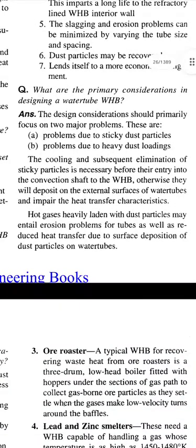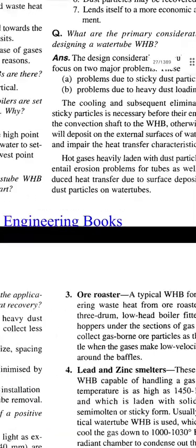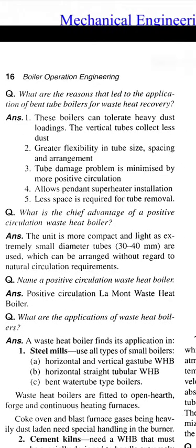Hot gases heavily laden with dust particles may entail erosion problems for tubes as well as reduced heat transfer due to surface deposition of dust particles on water tubes. Question. What are the reasons that led to the application of bent tube boilers for waste heat recovery? Answer. These boilers can tolerate heavy dust loadings.